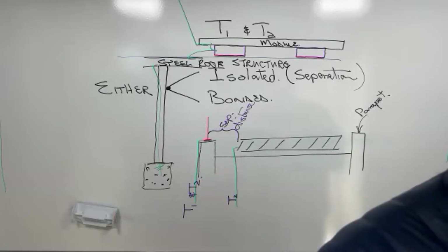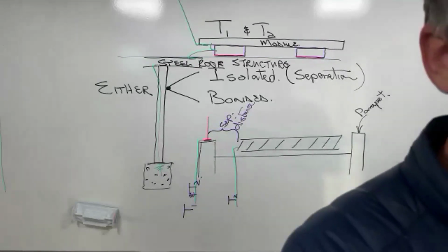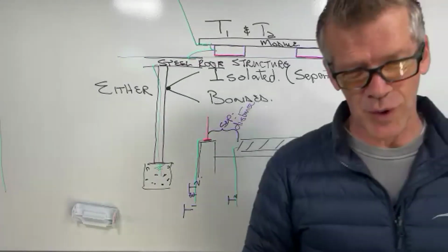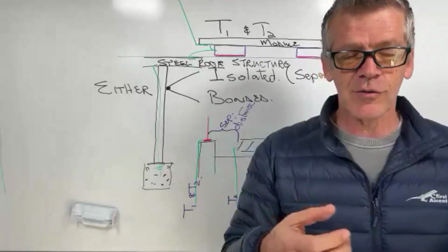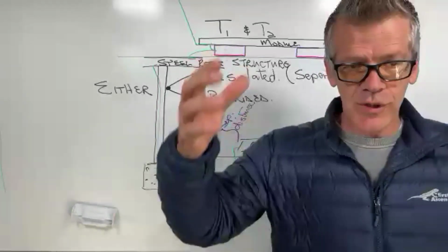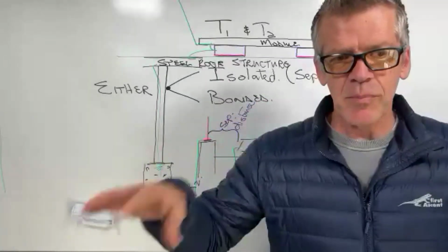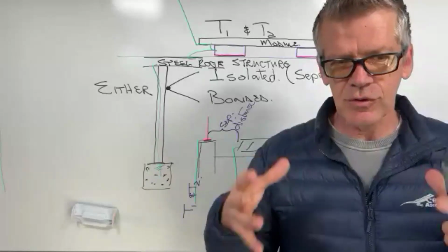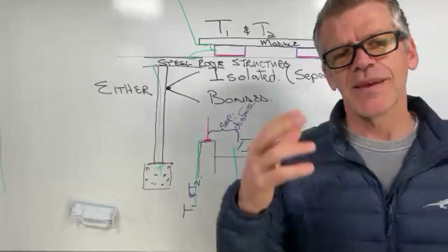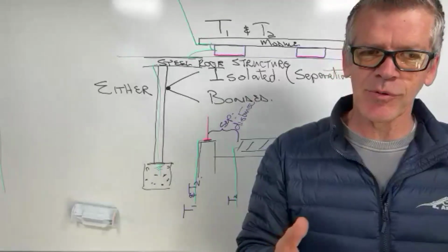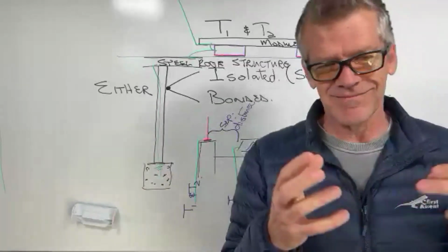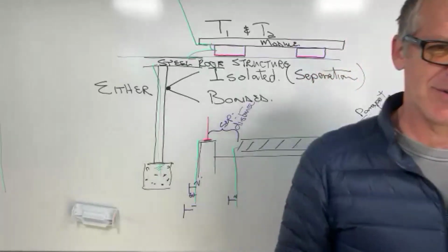Ntlantla wants to know whether copper bonding strip is allowed. Ntlantla, copper bonding strip would be allowed if you don't just use one bonding strip. So you'd have to use lots, because you're trying to get the square millimeter, or the amount of places where you can get that power to dissipate. You're trying to get more of those. So can the bonding strip work? Yeah, it can work. Is it ideal? Probably not.